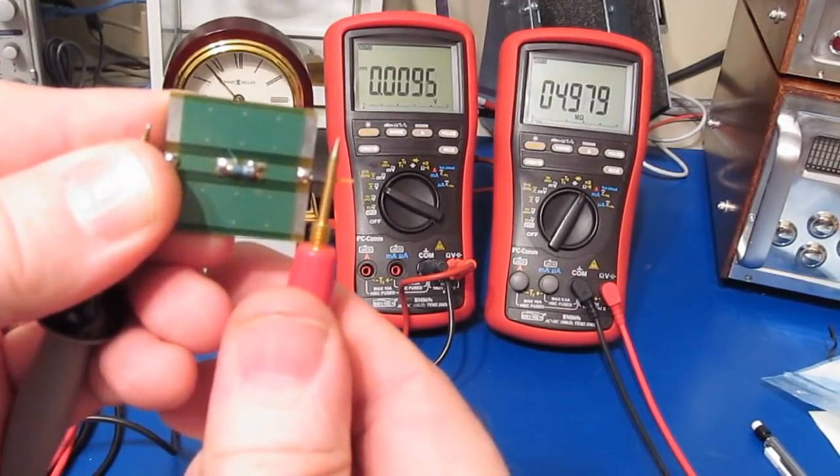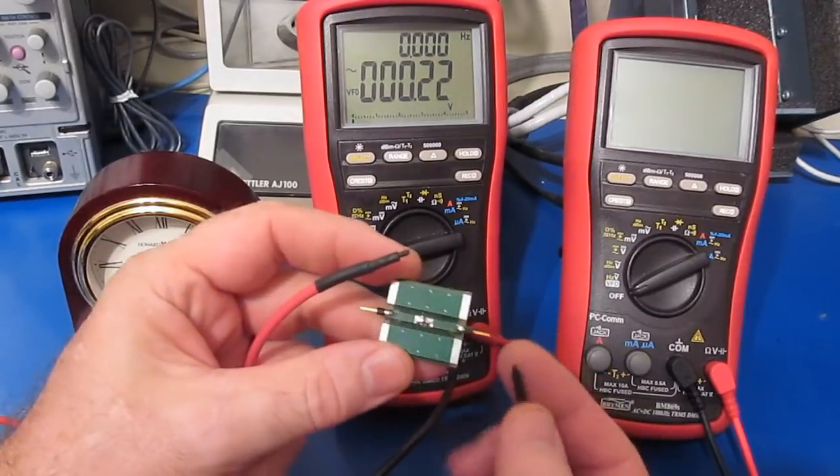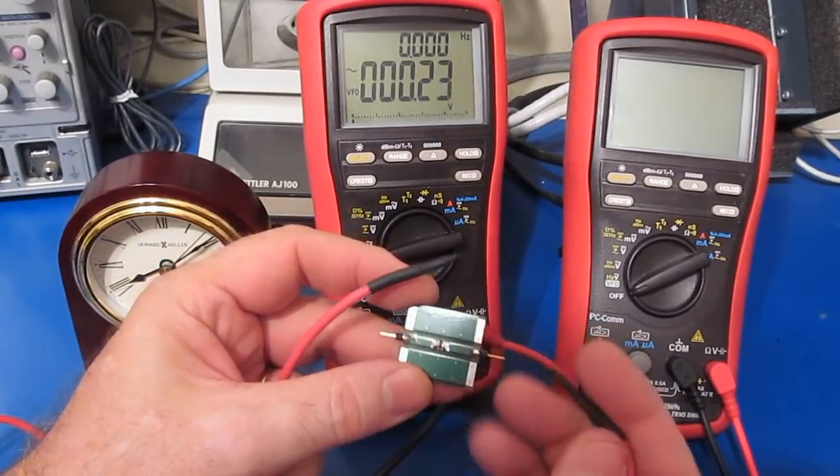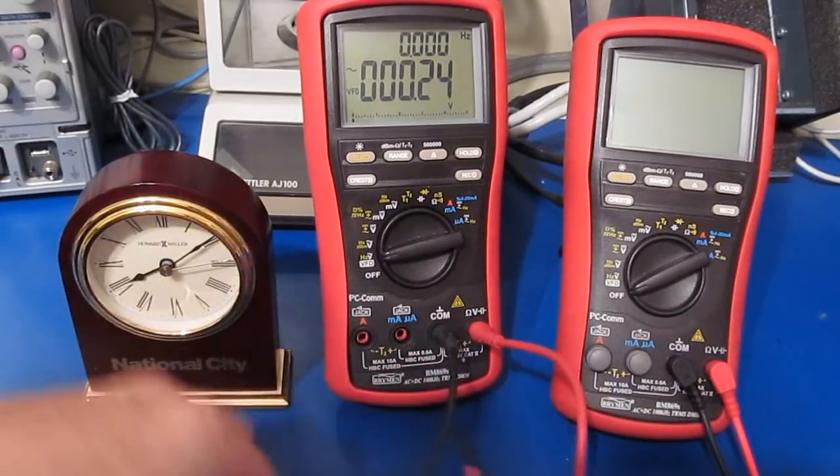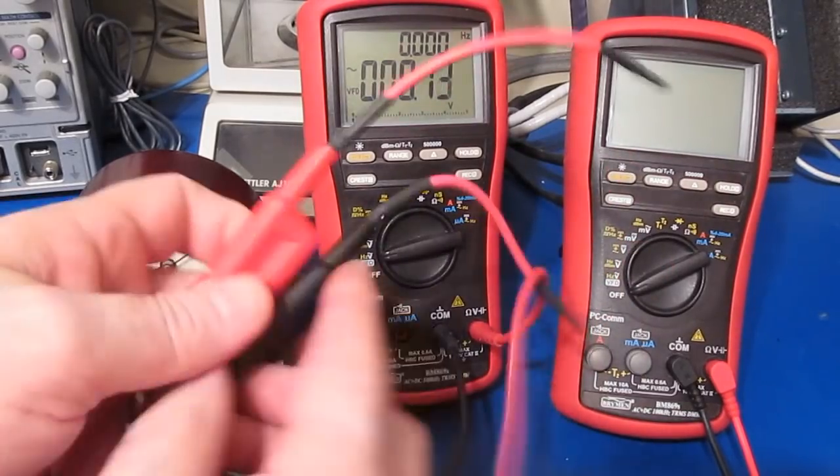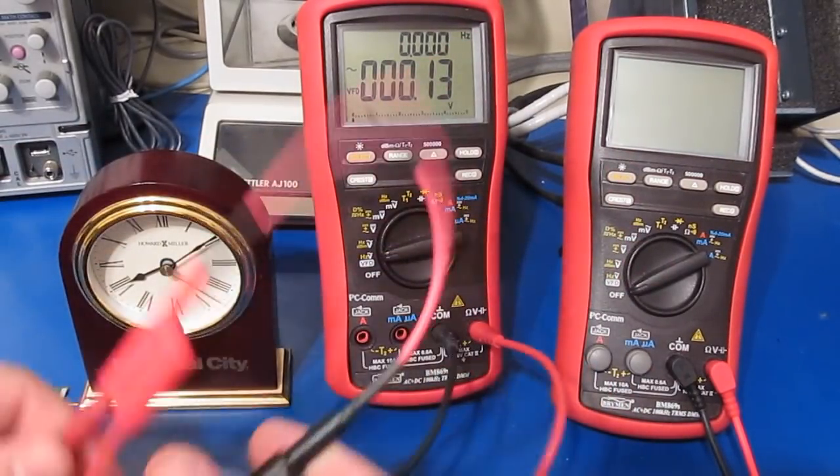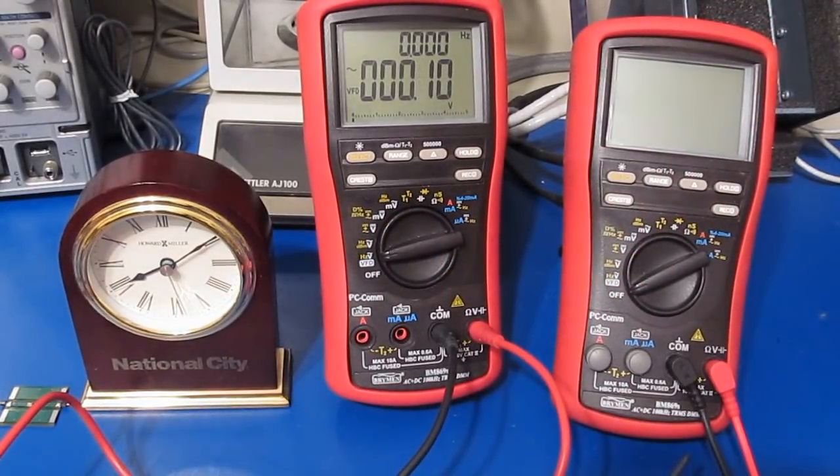Let's just go ahead and check the resistance. And again you can see it's still five meg. So again, the IEC standard calls for a 500 VA power supply to be used during this testing. What I've got here is our high power 1 kV power supply. The Brymen is no longer attached to the attenuator, it's just hooked directly to the output of our power supply.